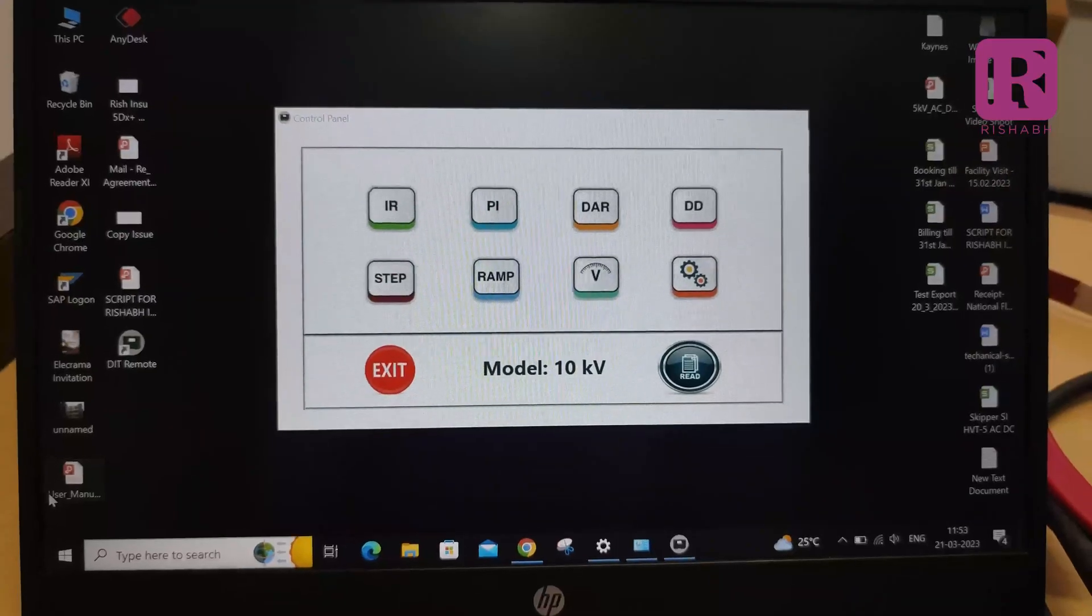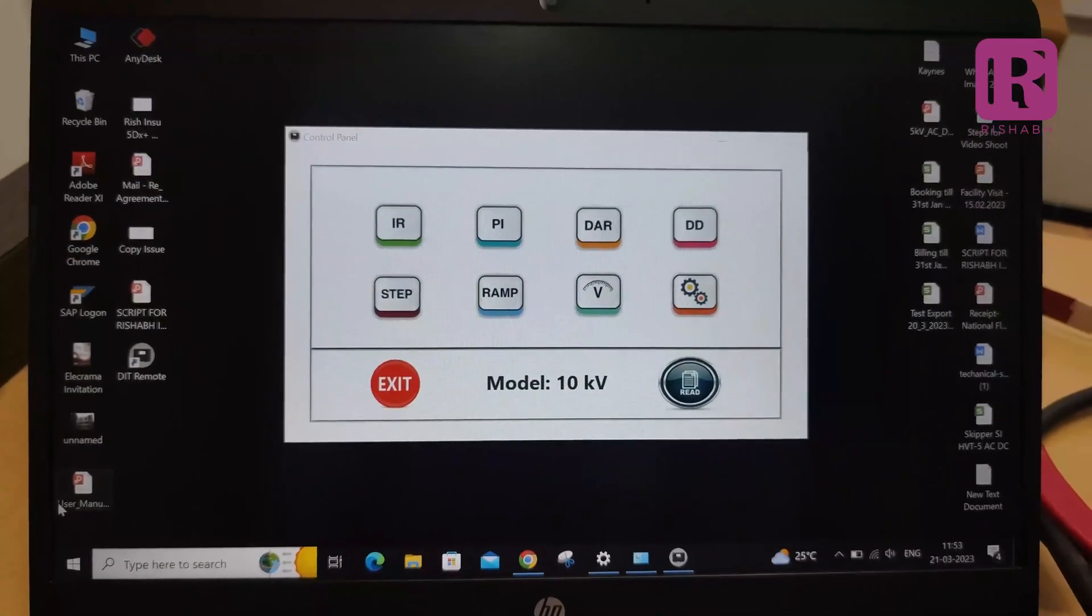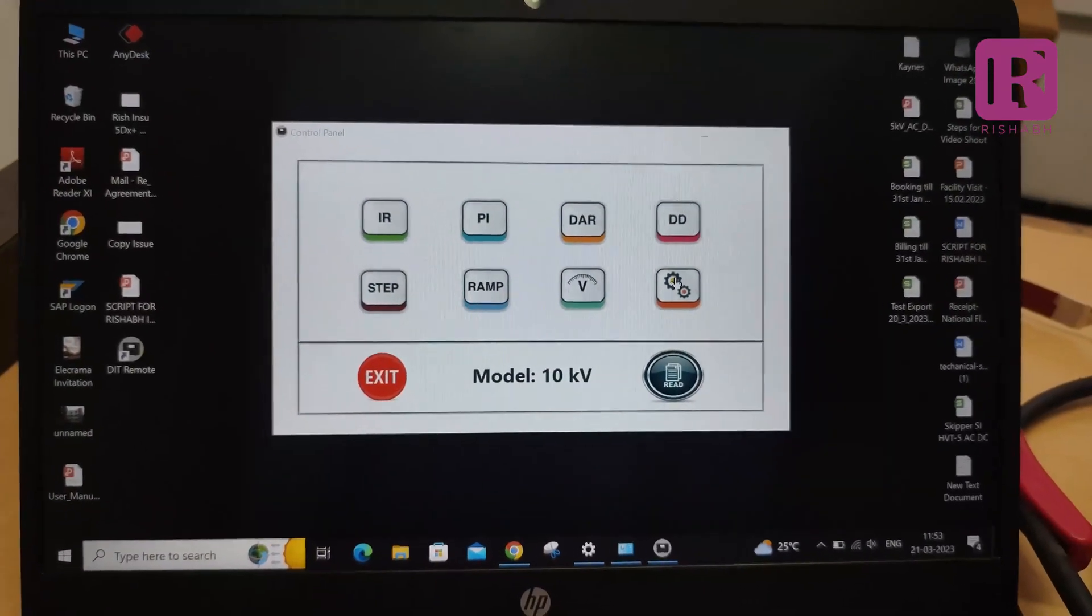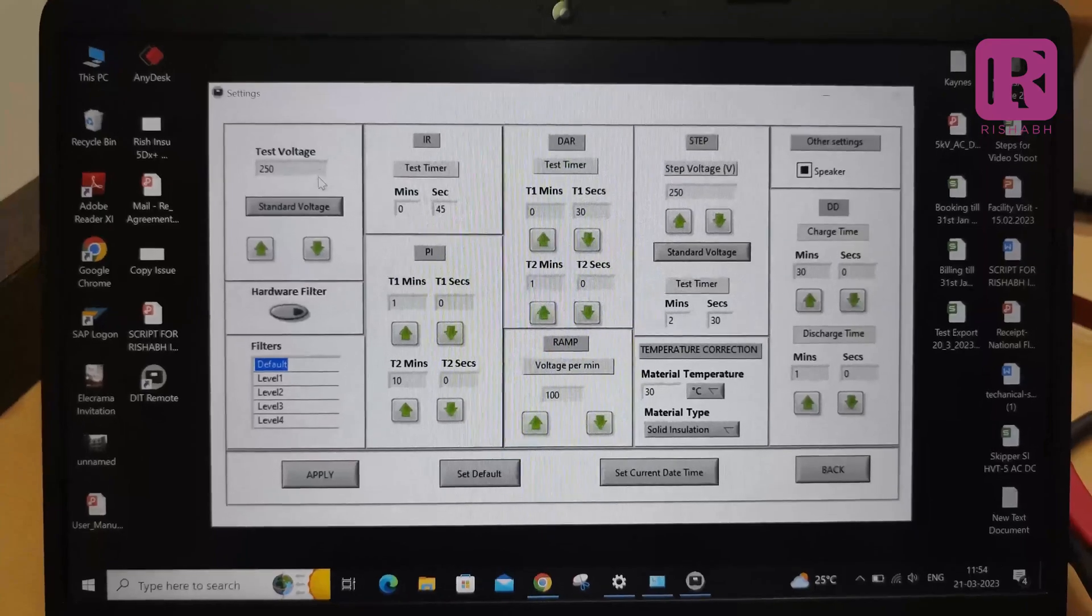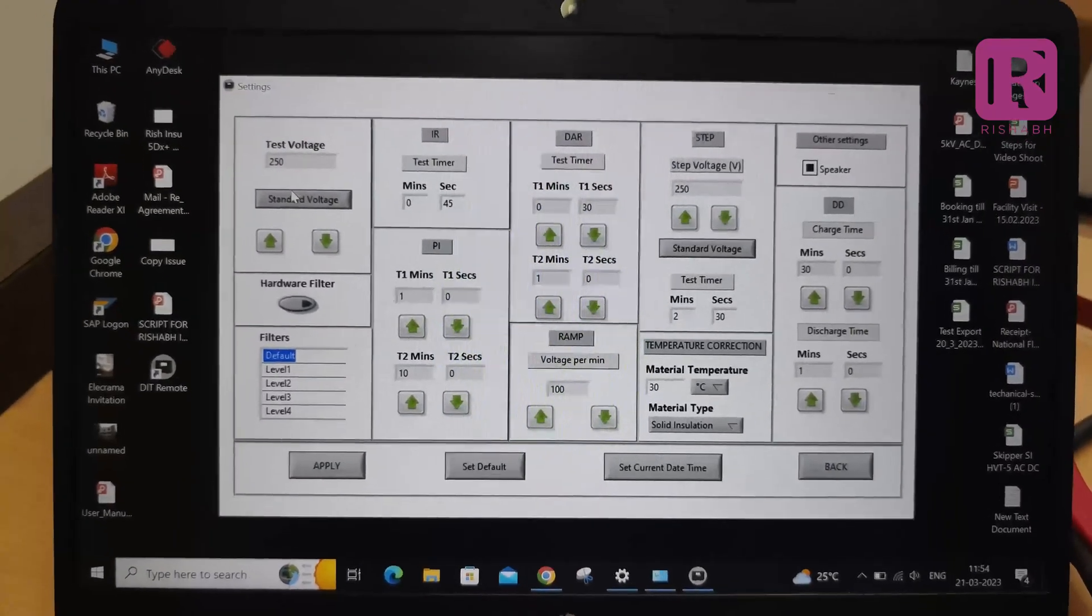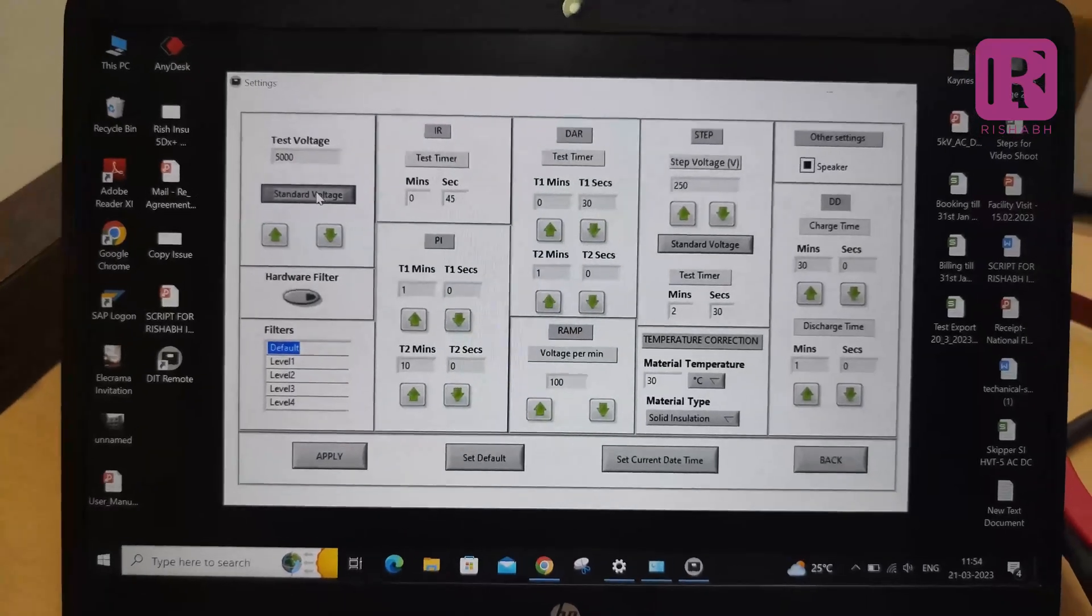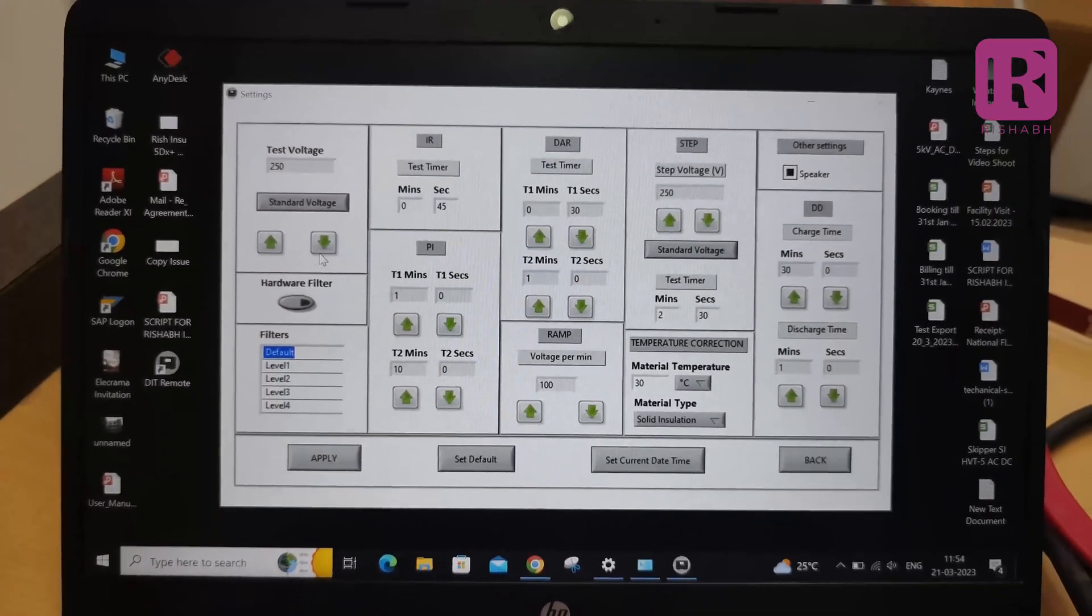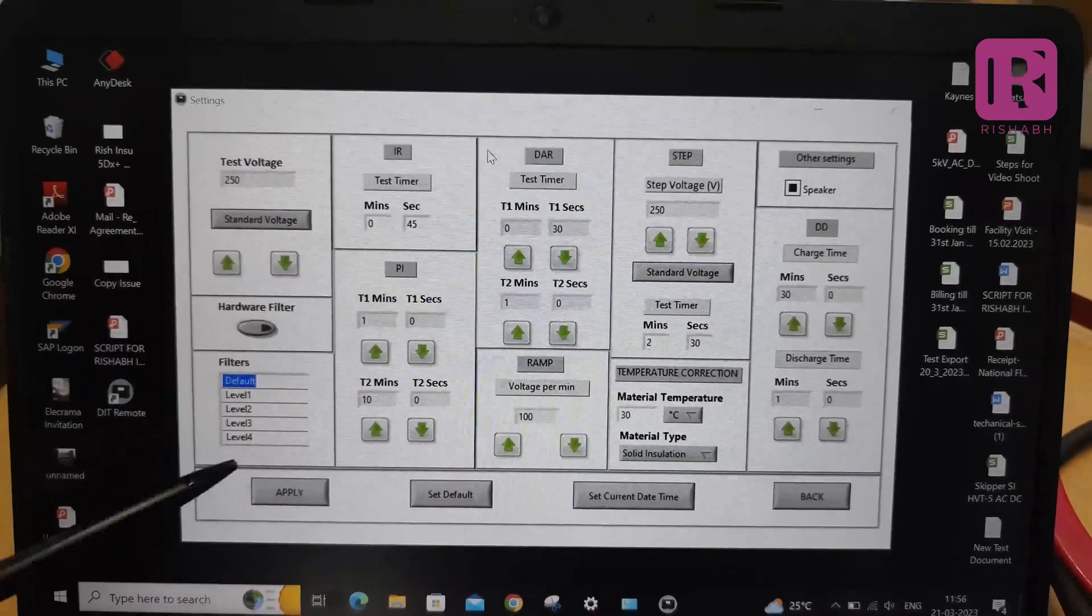Now, before going into IR or any other diagnostic mode parameter, initially we will go into setting parameter in the software. In the setting parameter window, you can see the test voltage setting with the help of standard voltage key and up and down arrow keys. You can select the hardware and software filters.